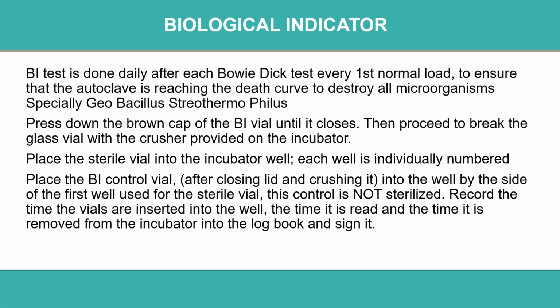So what is the procedure after sterilization? We will take it out after 10 minutes, after cooling down. We press down the brown cap of the biological indicator vial until it closes. Then proceed to break the glass vial with the crusher provided on the incubator. Place the sterile vial into the incubator well. Each well is individually numbered, so you should remember which one you are using for which cycle.